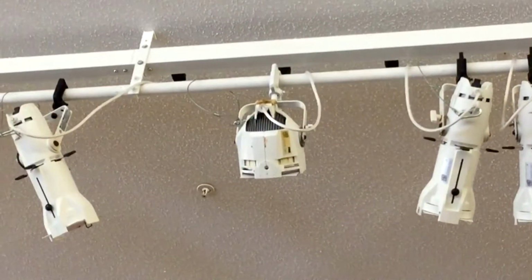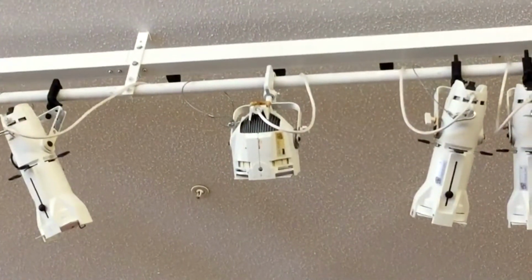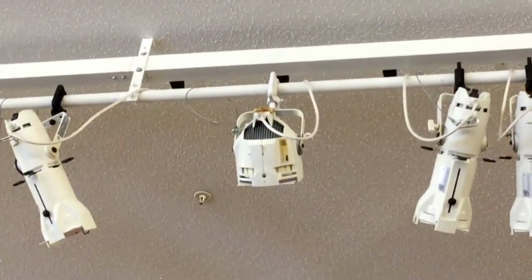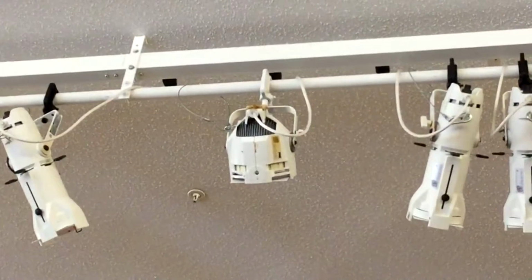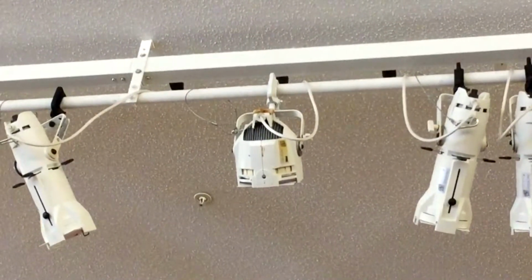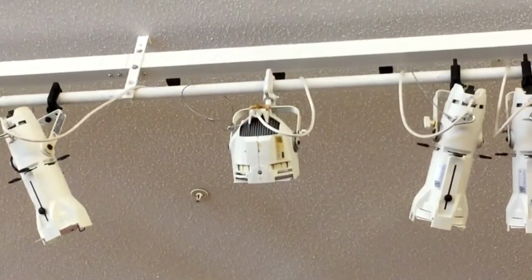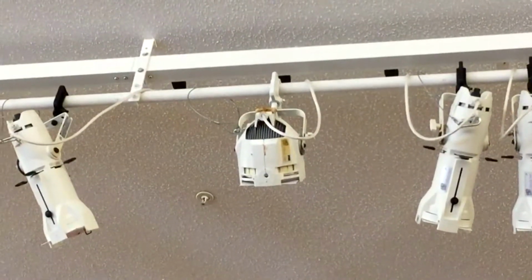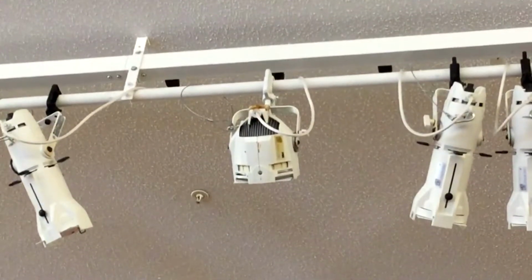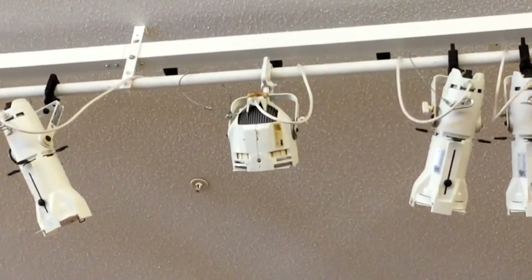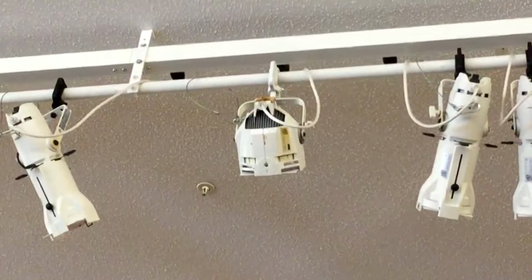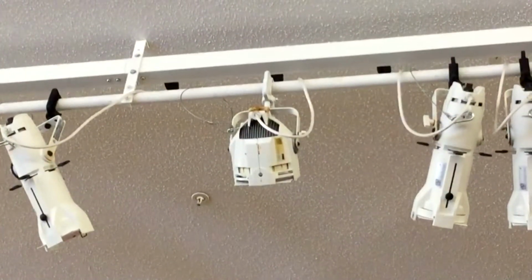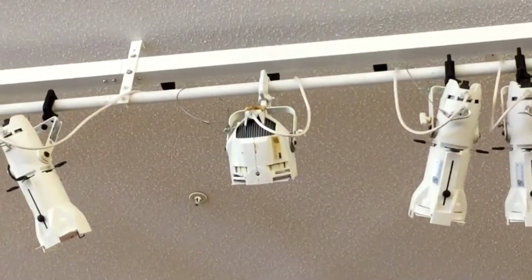Sometimes the bulb gets stuck due to heat cycles, and it's going to take some effort to pull the bulb out. When you put the new bulb in, do not touch the bulb with your bare hands. The oils on the glass will make the bulb prematurely fail. The way I do that, there is a padded sleeve that the bulb comes in. I hold the bulb by the padded sleeve, insert with the padded sleeve, stuff the thing in my pocket, and put everything back together and climb back down the ladder.